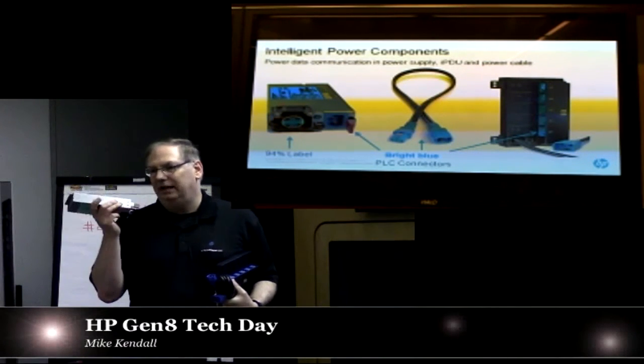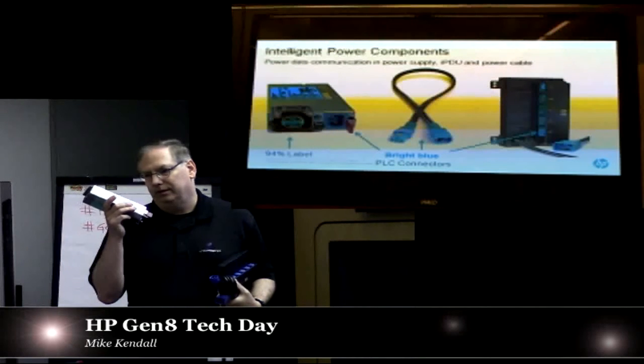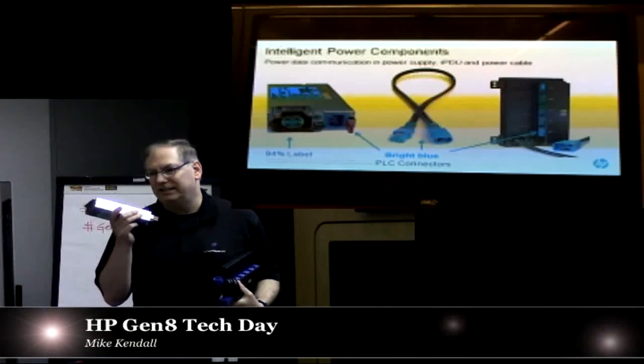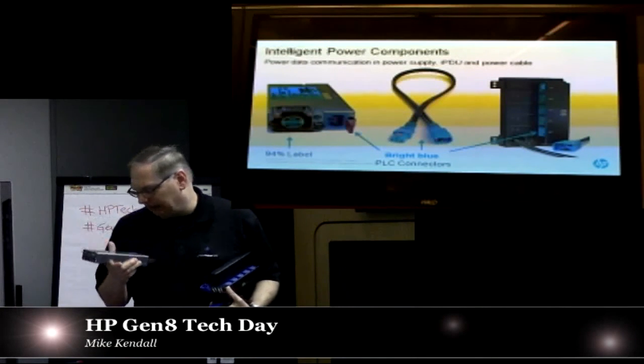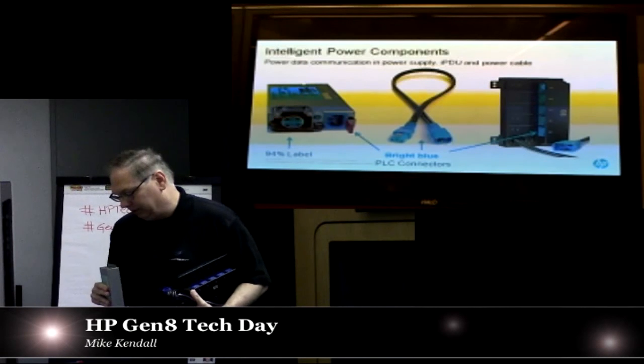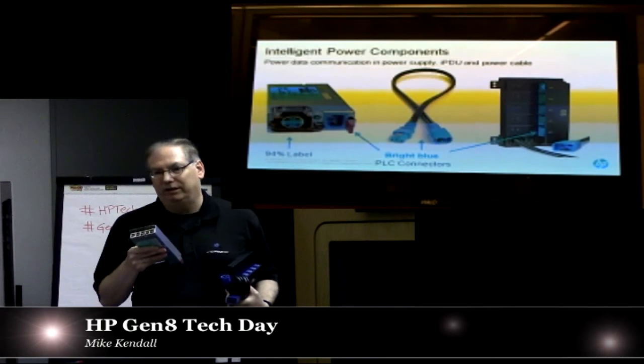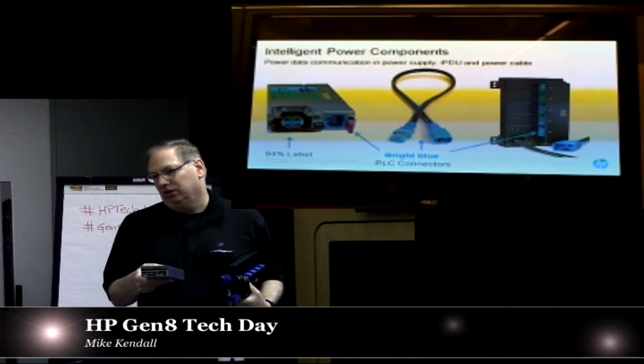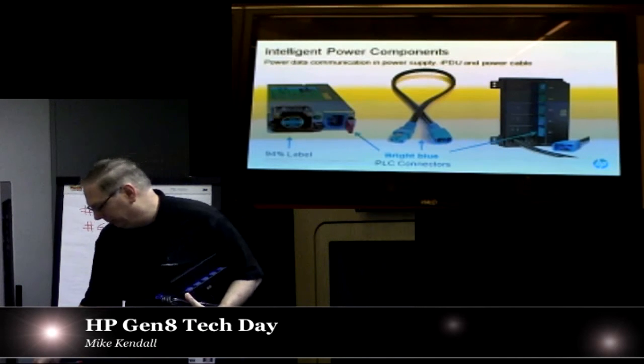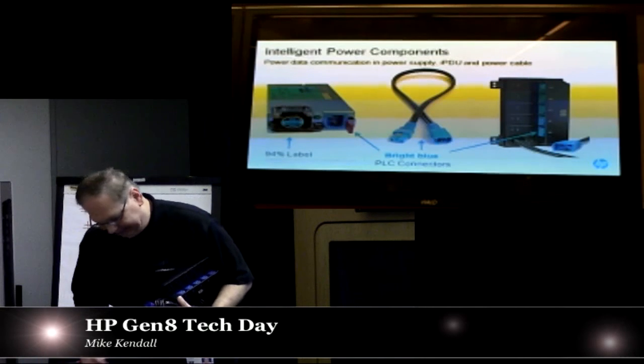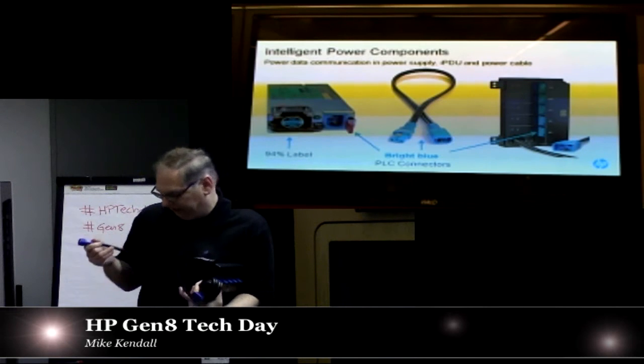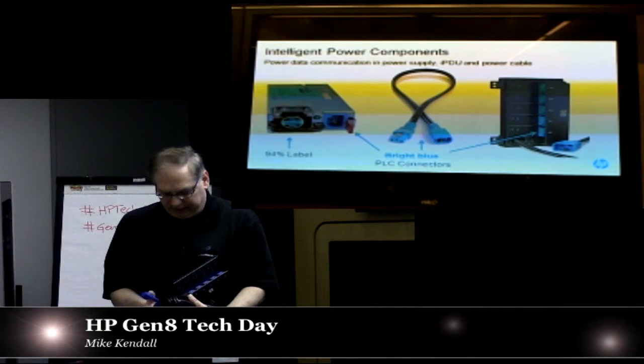So you've got the ILO talking to the system. The system knows exactly what power it's drawing at all times. That's another thing the PDU knows, is the power. It can correlate that with the states in the server and what the server says it's pulling, to make sure everything's accurate. That gets communicated off of this plug here, which then goes over and hooks into these sticks.